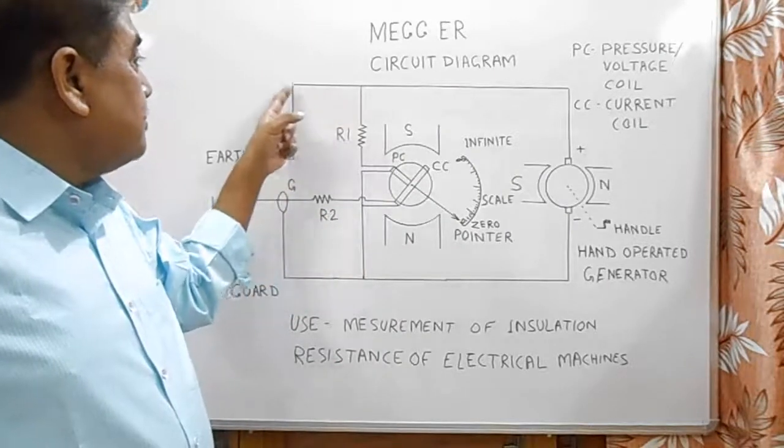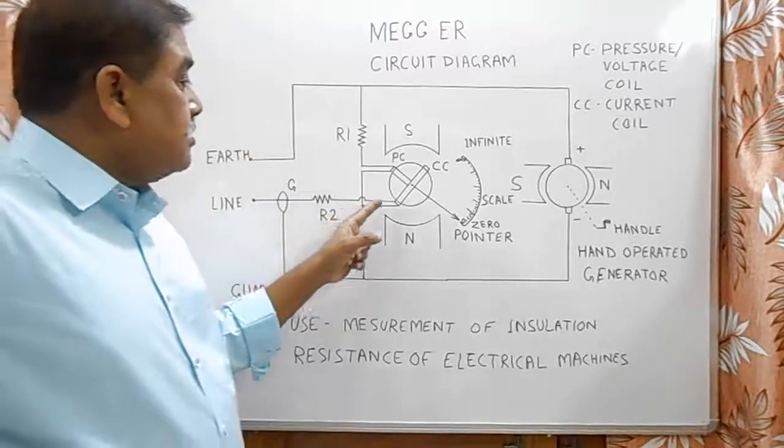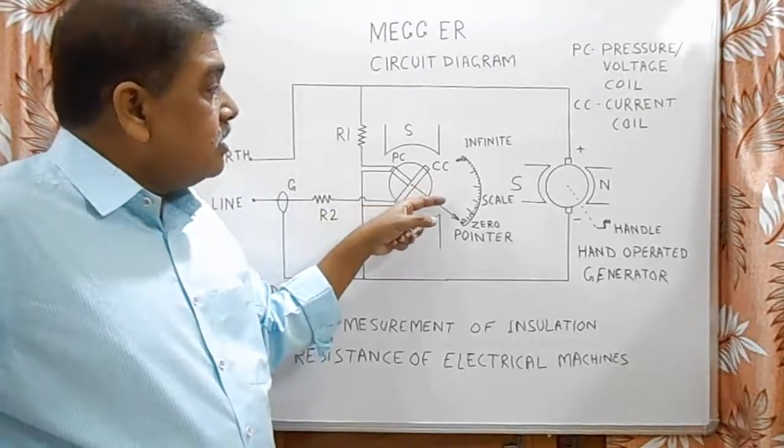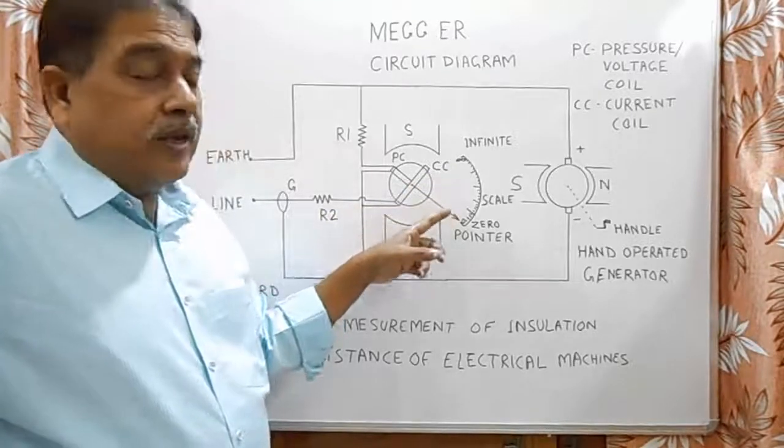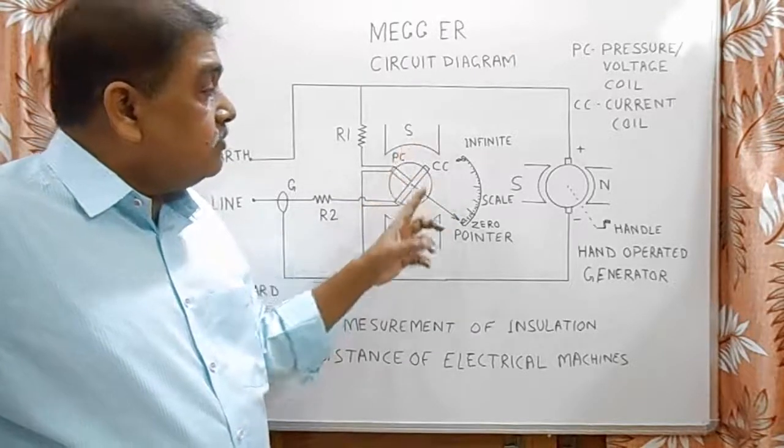When the pressure coil comes from this line through testing resistance to the R2 and returned back to the current coil. Current coil produces a torque in the direction of zero, and the pressure coil produces the torque in the direction of infinity.